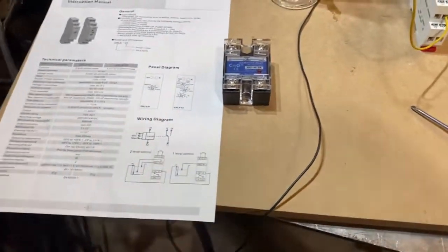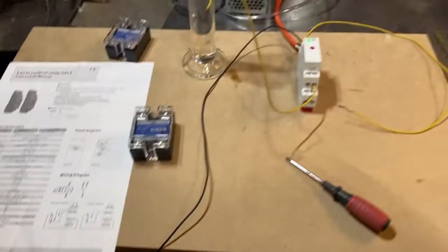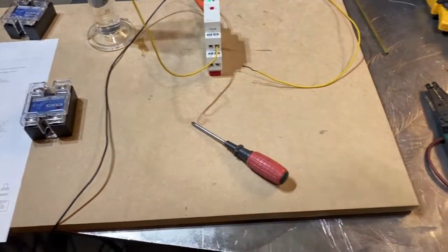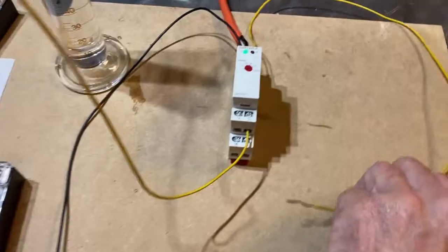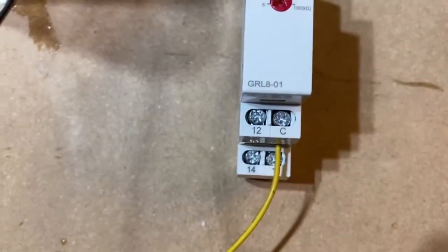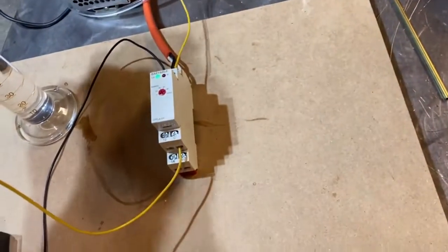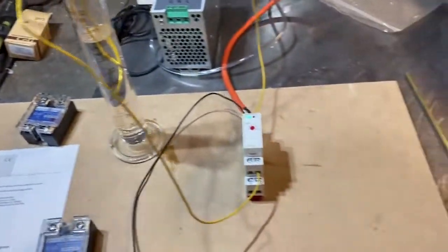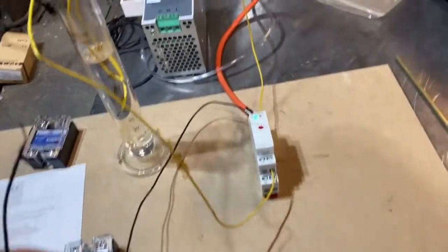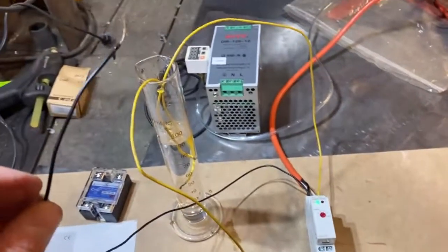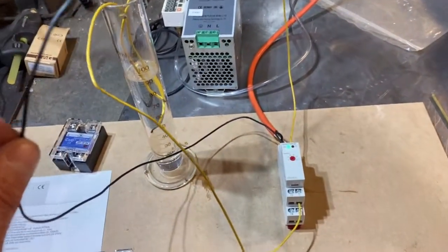Essentially, what you need to do to get it to work is you have to have both the minimum and the common submerged in the water. I'm just doing a test to get the thing proofed out. And then in order to get the relay to fire, you have to submerge the maximum.